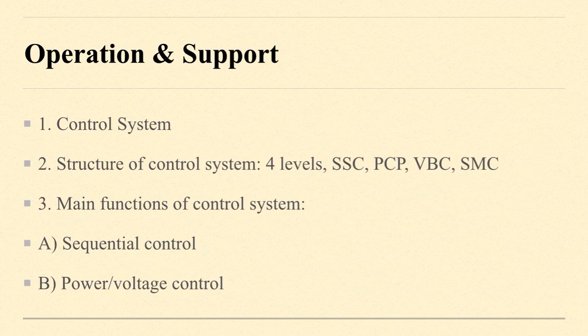First is operation and support. First is control system. The structure of control system can be divided into 4 levels. Firstly, system level control (SSC). It is the highest level of the control system. It can take SCADA commands and realize the communication among control system and converter stations. It can generate power commands and operation mode commands, and then issue them to converter level controller.